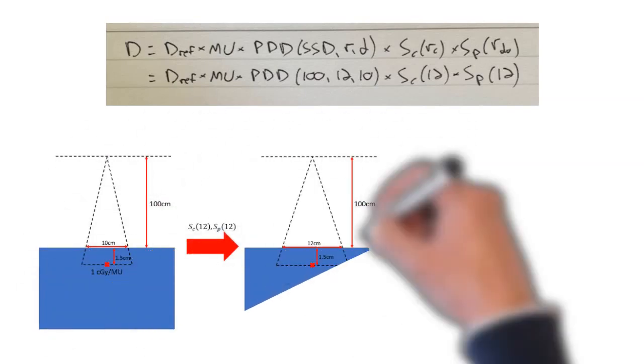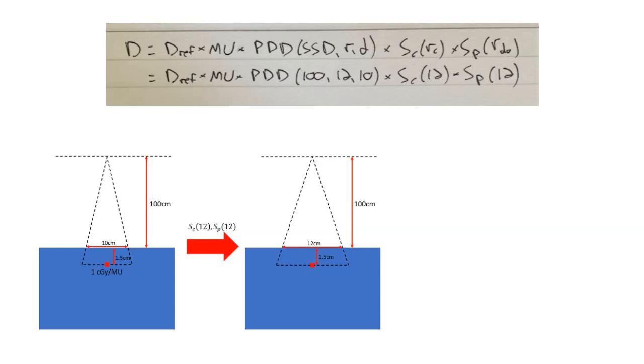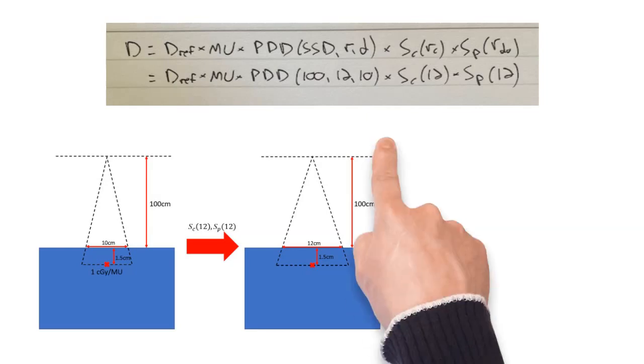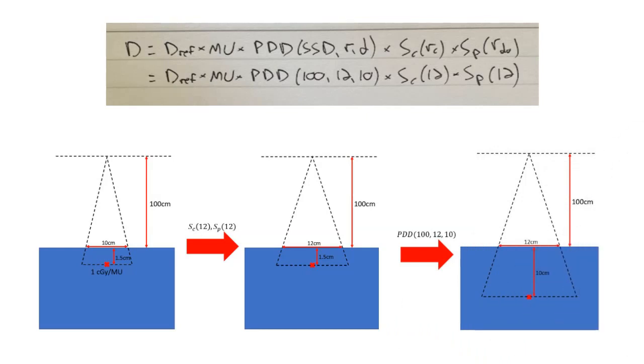I always find it extremely helpful to draw out how we are perturbing our reference condition, and that's what I'm doing here. On the left we have our reference condition — the LINAC was calibrated at 100 cm SSD at a depth of D-max for a field size of 10×10. When we apply a collimator and phantom scatter factor to that geometry, we are just increasing our field size, as shown in the middle. So we have the same SSD but the field size is now changing while we're still at the same depth. Then with the PDD at 100 cm SSD, field size of 12, and depth of 10, we are moving the calculation point deeper in the phantom — from D-max at 1.5 cm down to the 10 cm depth that our problem asks for.